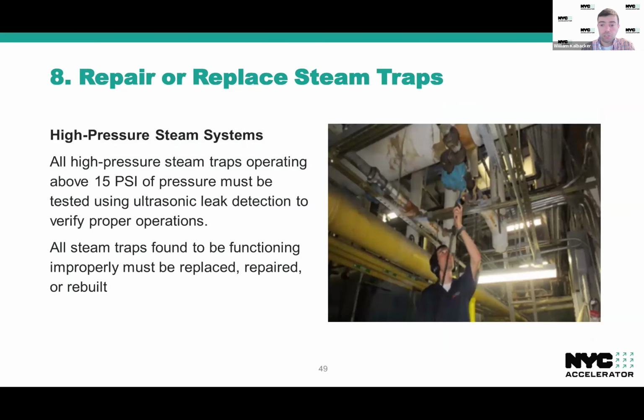Just one special call out here for the testing protocols for high pressure steam systems. High pressure systems are sort of their own beast, and testing of high pressure traps is going to require specific use of an ultrasonic leak detection system instead of maybe a combination of ultrasonic and thermal testing. So it's specific to high pressure systems only. And again, any trap that's found to be not properly functioning needs to be repaired or replaced.